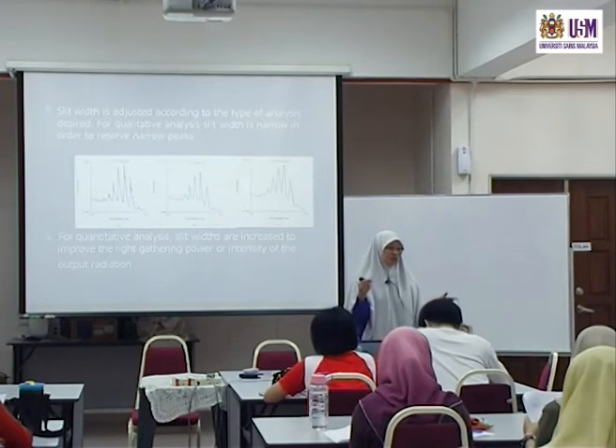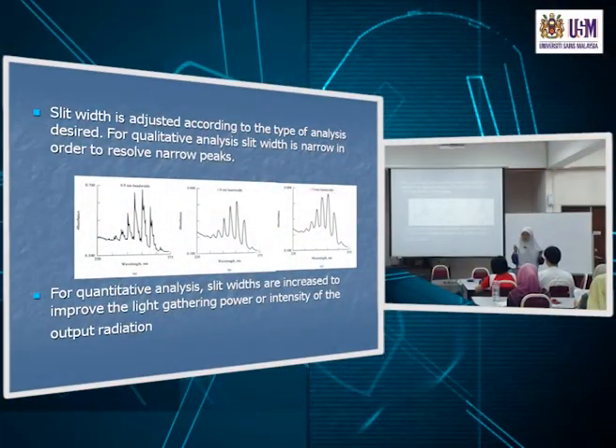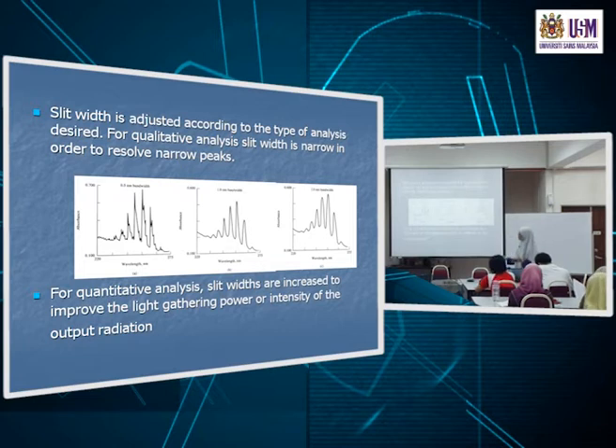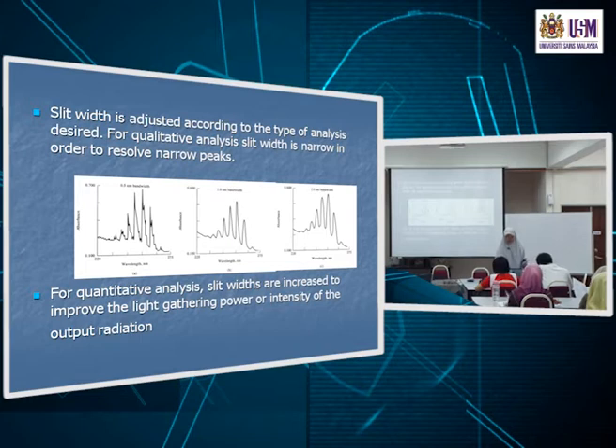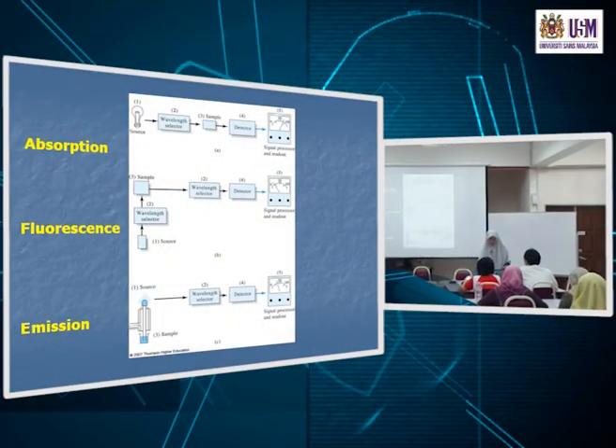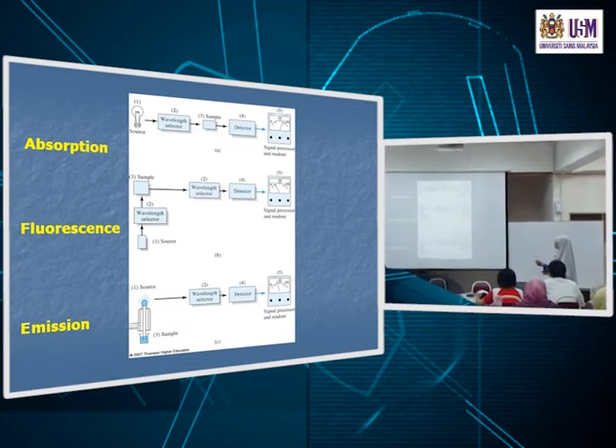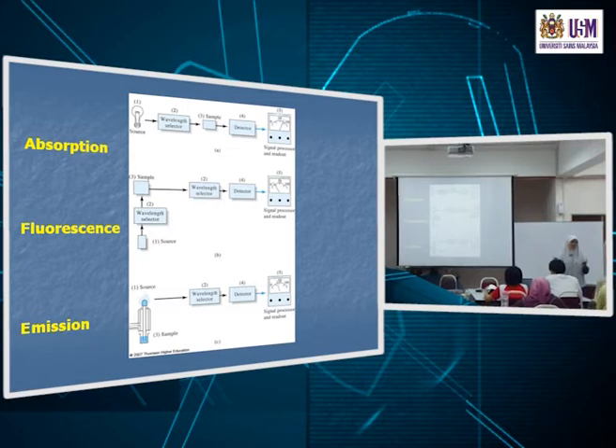For a particular monochromator you have a particular linear dispersion characteristic D⁻¹. The bandwidth depends on both slit width and D⁻¹. We have seen how slit width affects resolution and effective bandwidth, and which slit widths are required for qualitative versus quantitative analysis. We are now going to leave the monochromator and move on to detectors.